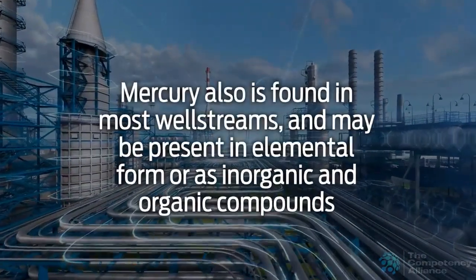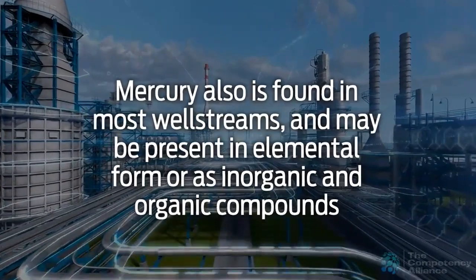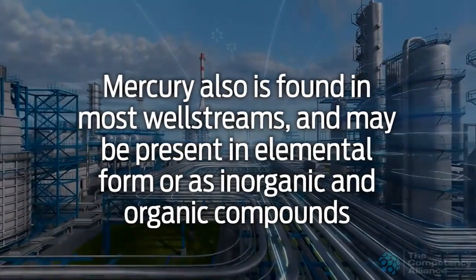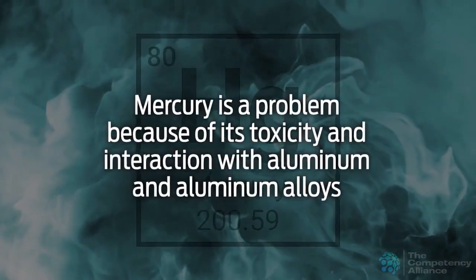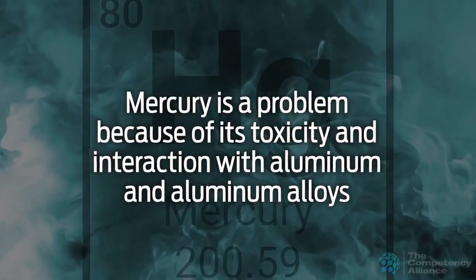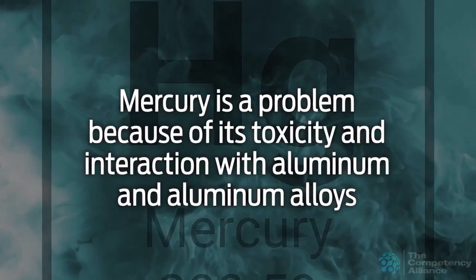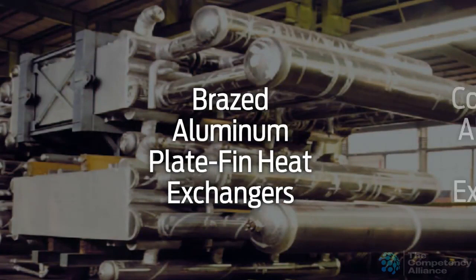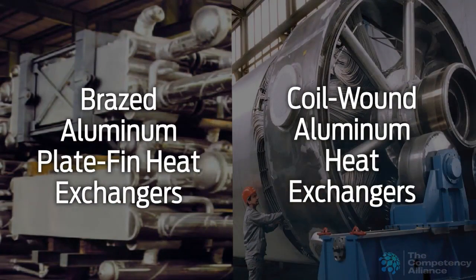Mercury also is found in most well streams and may be present in elemental form or as inorganic and organic compounds. From a gas processing viewpoint, mercury is a problem because of its toxicity and interaction with aluminum and aluminum alloys. Brazed aluminum plate fin heat exchangers (BAHX) are widely used in low-temperature gas processing plants, and coil-wound aluminum heat exchangers are widely used in LNG liquefaction plants.